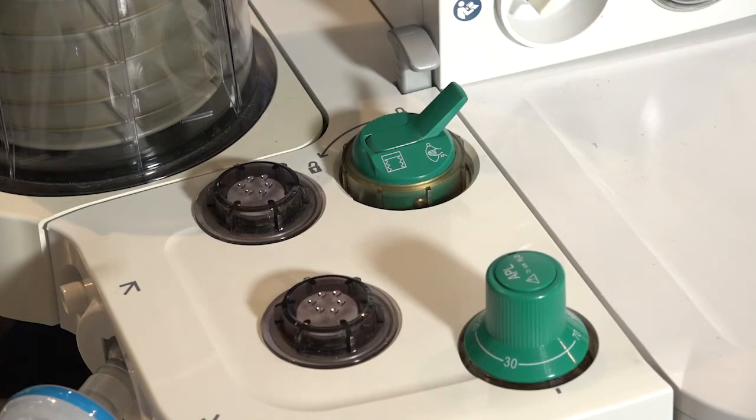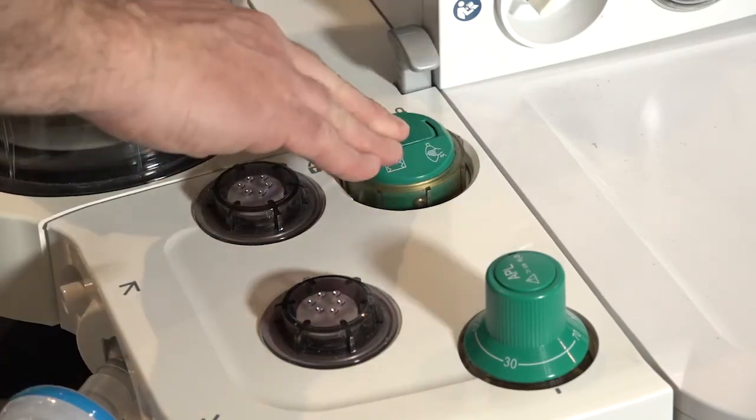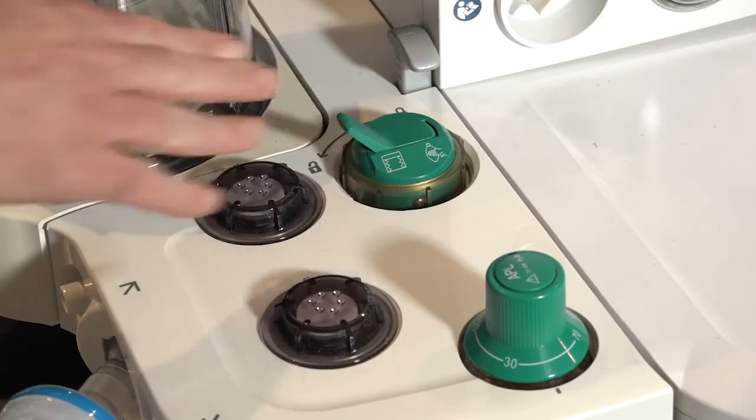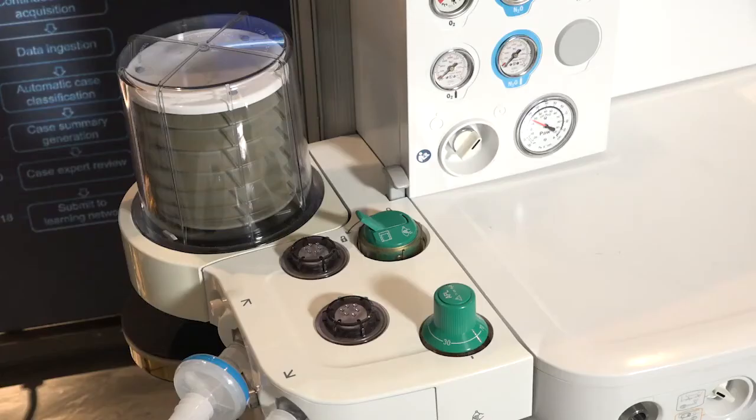Mechanical ventilation begins by moving the bag to vent switch to the vent position. Ventilation will begin at the previous configured or default settings.